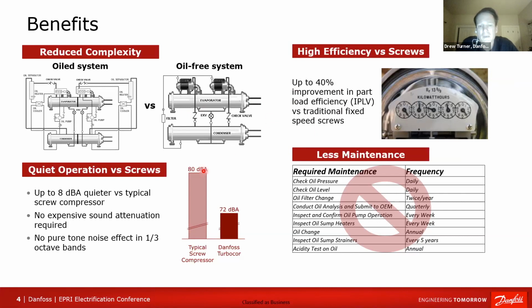The other thing that it drives, and this was a part of the goal, but it's really a byproduct of the technology solutions that enables oil-free, is that if you have centrifugal or dynamic compression and magnetic bearings, those 2 portions of the front end and the back end of the compressor are the main noise generators. If you eliminate those, then you eliminate all the noise that comes from those because you have no metal-to-metal contact.